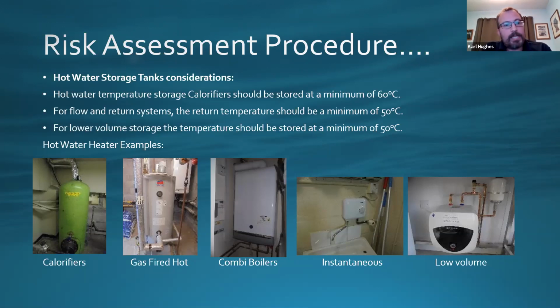The calorifier on the left-hand side is a higher risk because you've got the cold water coming in at the bottom, and you've got an area within the middle where you've got the ambient temperature for Legionella proliferation. The gas-fired one at the bottom, you've got obviously the burners underneath, so it's heating the water from the base where the cold water's coming in, so it's doing its damage there. You've got the combi boiler, an instantaneous one where there's no stored water, and the low volume ones there, which you maintain at 50 degrees.